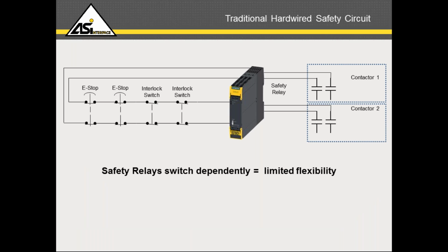Also keep in mind that the function of the safety relay when it's hardwired like this is really dependent on the configuration of the hardwiring of the attached inputs and outputs. So system flexibility is really limited, both in terms of functionality, and if you think about future expansion, you're really pretty limited if you've hardwired it.